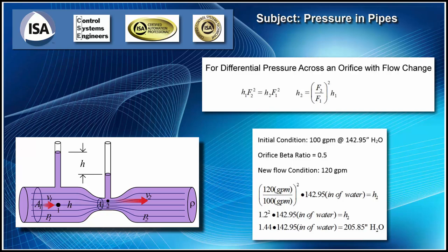And so as you notice, since our work is based on the flow squared, the head changes as a squared function. So when we're at 50% head, we're actually at 70% flow. And so it just keeps increasing. If you're at 25% head, you're at 50% flow.